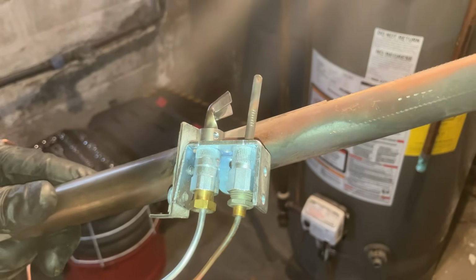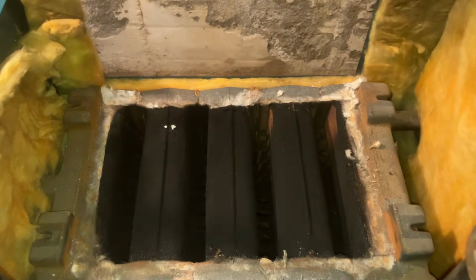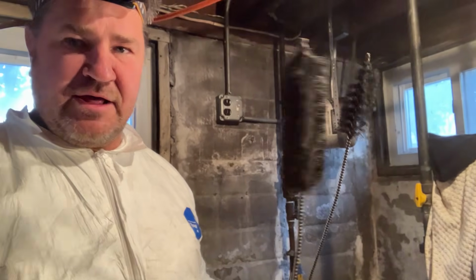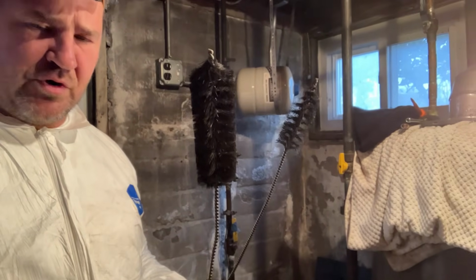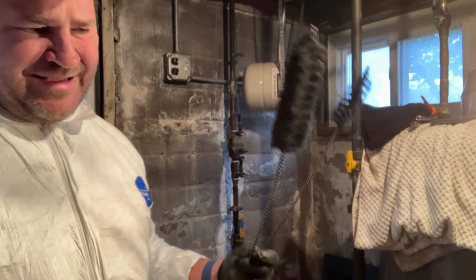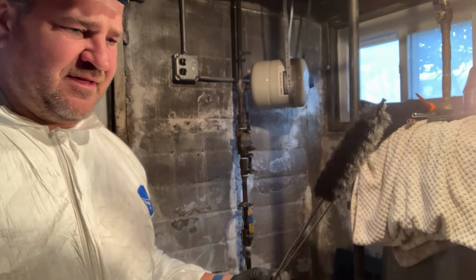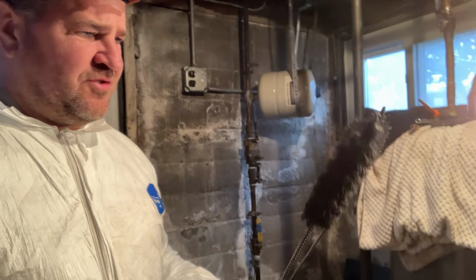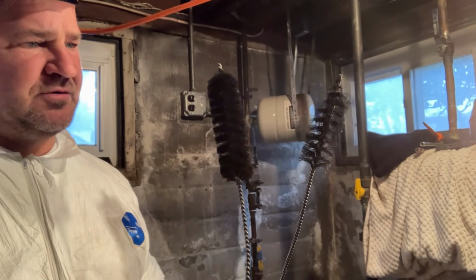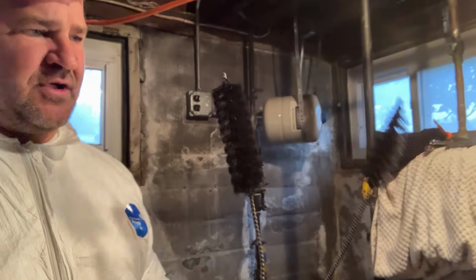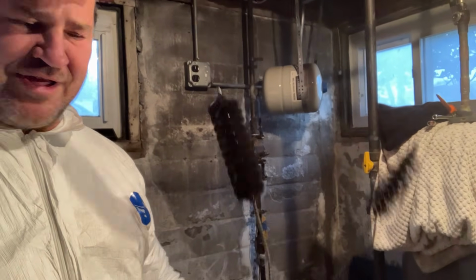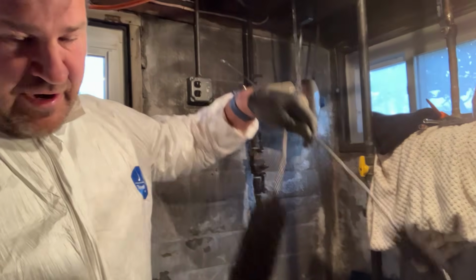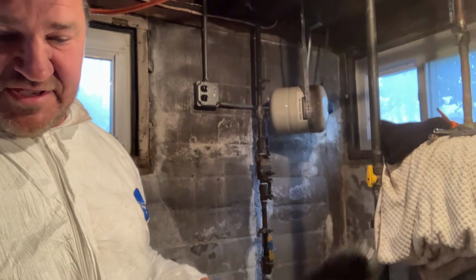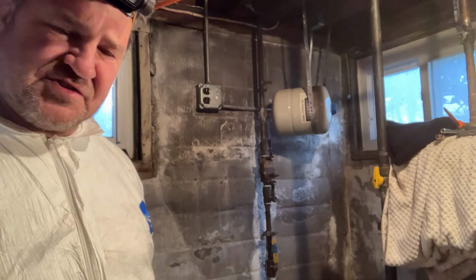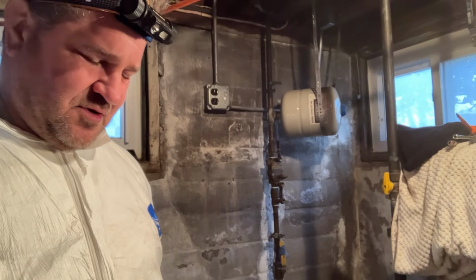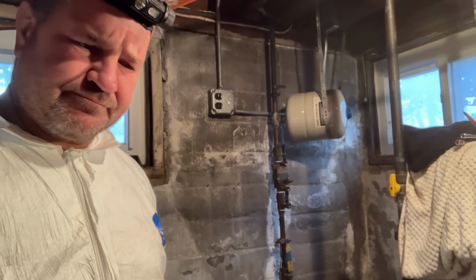Let's put this off to the side with the rest of the burners, set up our soot vac, and get scrubbing. All right, I'm gonna primarily focus on 2 brushes. I'm not worried about any kind of corrosion inside the boiler. So I have a smaller diameter brush, a thicker one. We'll start with the smaller one. I'm gonna go straight in, down on an angle, and you'll see what we take out of this disgusting boiler. Here we go.